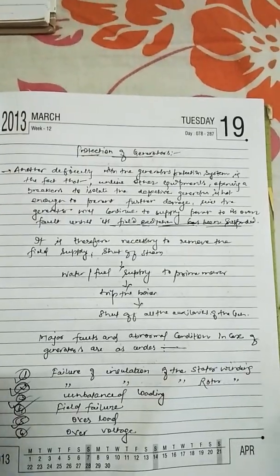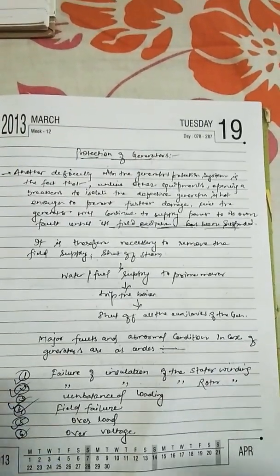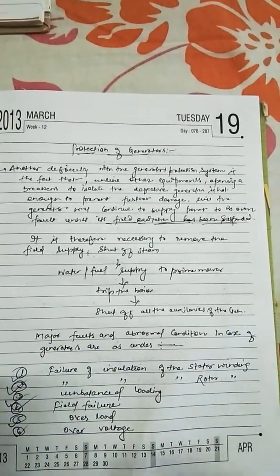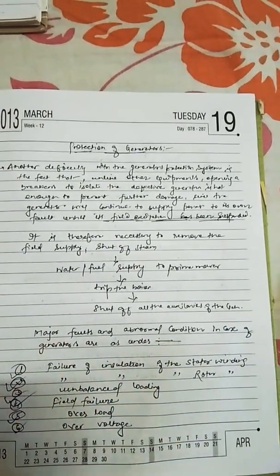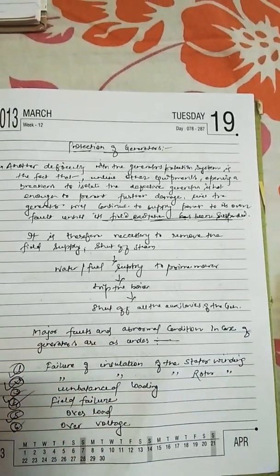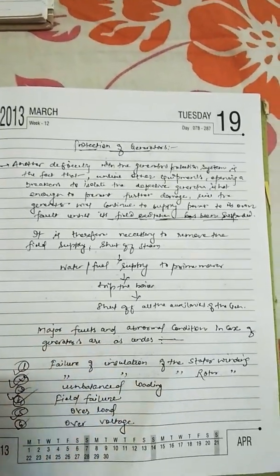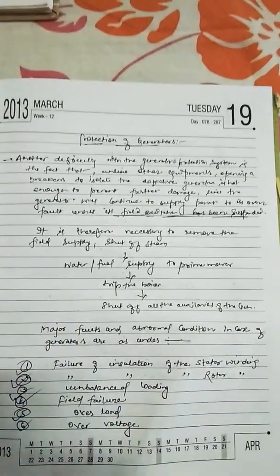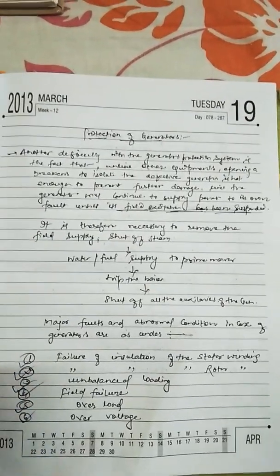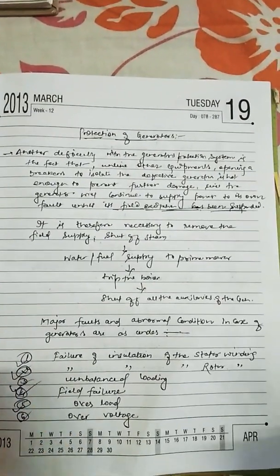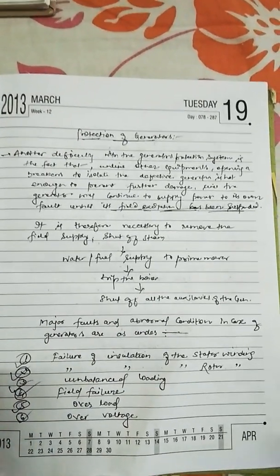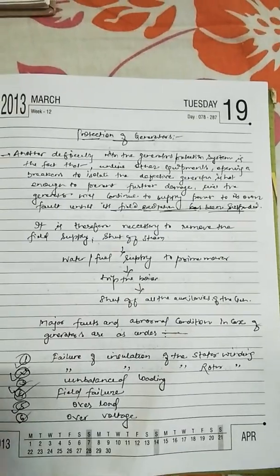However, it is not always necessary to isolate both the grid and the excitation and prime mover. Sometimes we have grid faults in which we need to only isolate the grid and run the generator on home load. For that, we have a generator protection philosophy where we divide the protection. Let us discuss what the major faults in generators are.